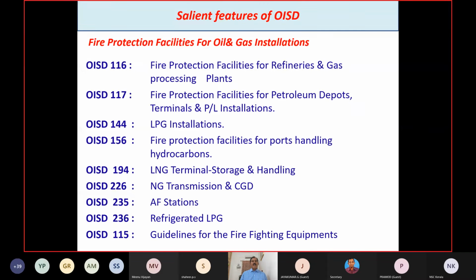Now let's move on to this next slide. See, fire protection is also very, very important as far as the oil and gas industry is concerned, because fire is the major hazard. So they have developed many standards for firefighting facilities, and it describes the design aspects and also the details of various firefighting equipment to be provided for the petroleum industry. The design aspects mean you can do design calculations for fire water. They have given a guideline for how to calculate the fire water demand. So if you go through this, you can compare the design for fire water calculations with your own unit, or you can develop on your own also.